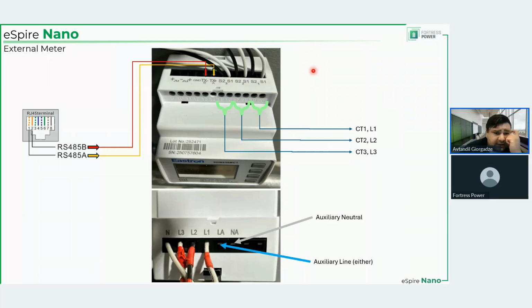This is slightly easier, especially considering that in this case I have the ability to speak to it rather than leave everything to the paper. So RS-485B would connect to TXB plus, and RS-485A will connect to TX, or I'm sorry, the B is minus and A is plus. This is the cable that you will run from the meter port on the inverter to the meter.